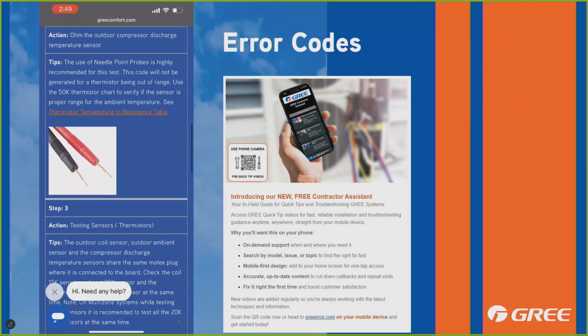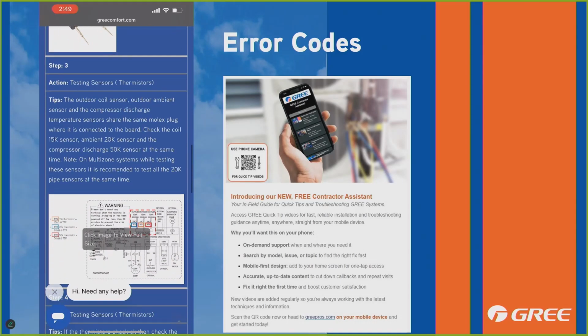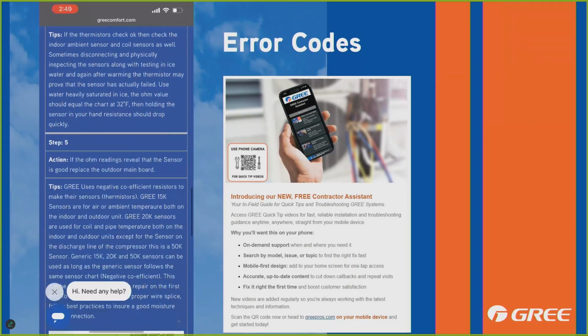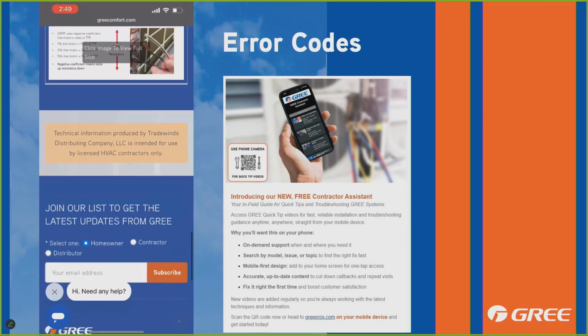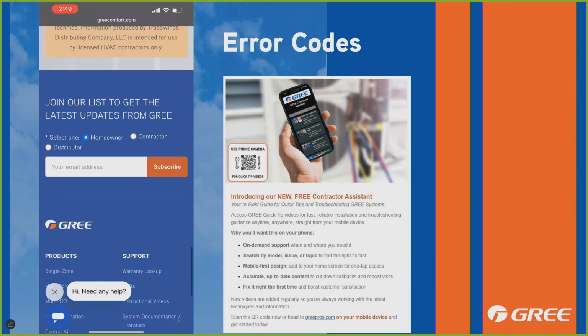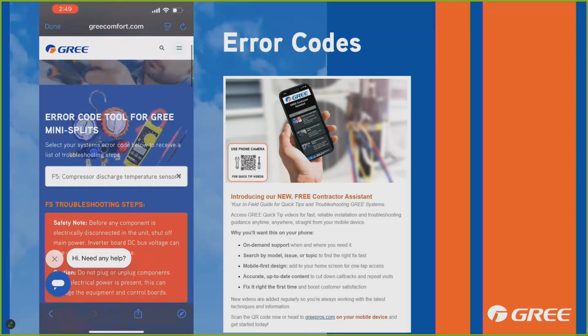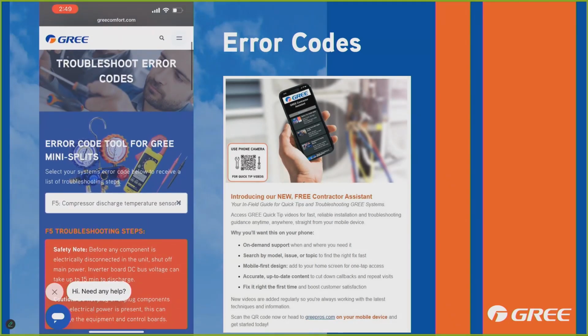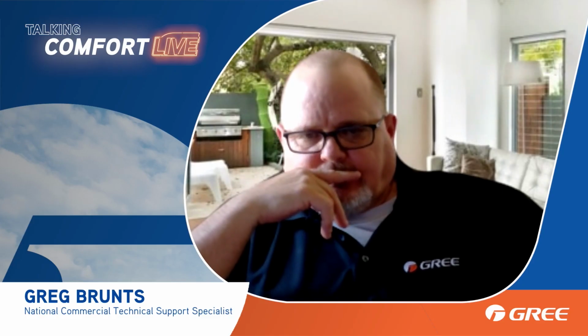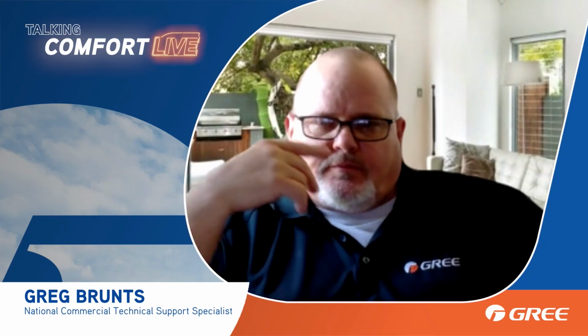What the error code means is that you've got a discharge temperature sensor error code. Just a personal note here, well over 9 times out of 10, if you've got a sensor error code, it's going to be that the sensor is open or short. But we give you the method to test that, to ohm out the sensor to ensure it is open or short. If it is open or short, what do you do? You've got to replace it. That's it.